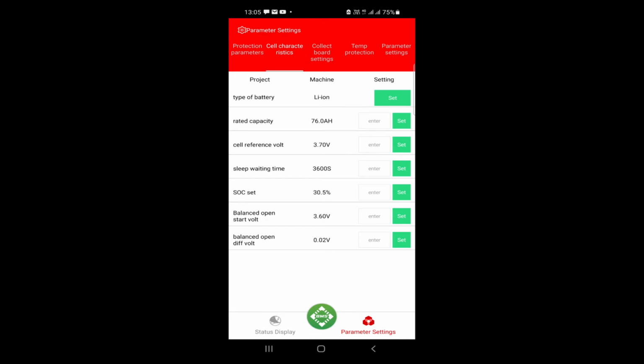Rated capacity depends, again, on the number of parallel connections. 76 ampere hour I have set. Cell reference voltage 3.7 volt. Sleep waiting time 3600 seconds. SOC set, this I will let you know how to set. Balance open voltage 3.6 volt. When a cell voltage reaches 3.6, it will start the balancing. And the balance open difference voltage I have set to 0.02, which is the lowest I can set here.